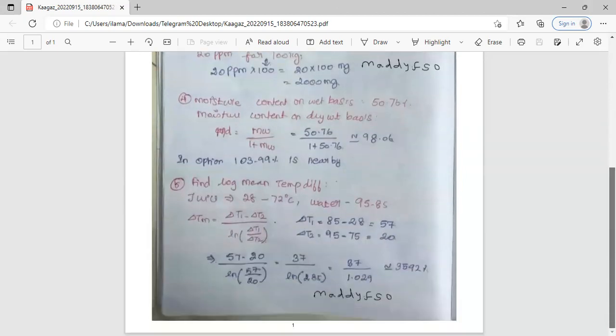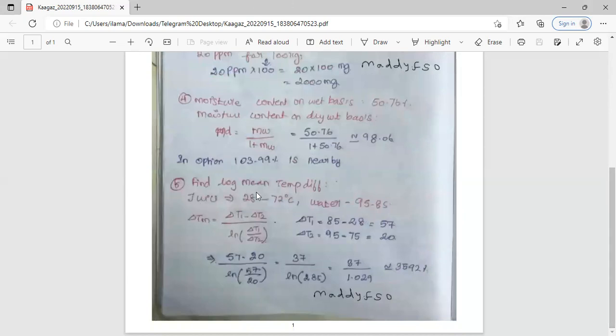For log mean temperature difference, the juice inlet temperature is 28 degrees Celsius and outlet temperature is 75 degrees Celsius. I mentioned that wrongly, marked it as 75 degrees Celsius, not 72 degrees Celsius. For water, inlet temperature is 95 degrees Celsius and outlet temperature is 85 degrees Celsius. This formula is the basic formula we have to know: del Tm equals del T1 minus del T2 divided by ln of del T1 divided by del T2.